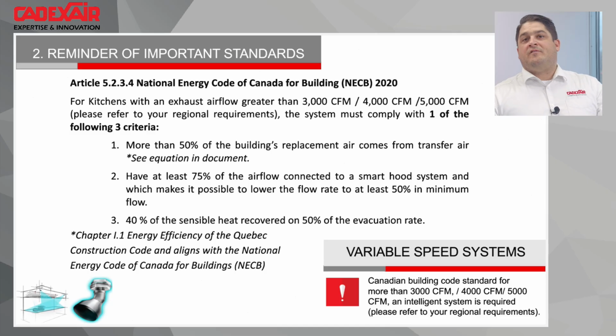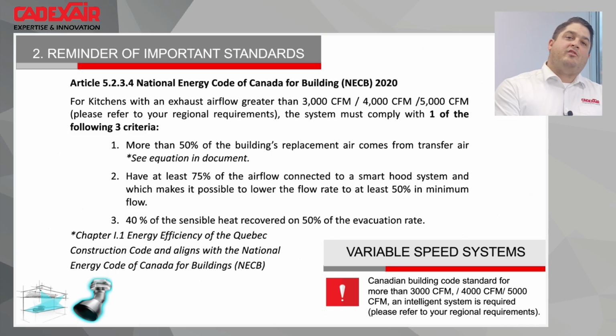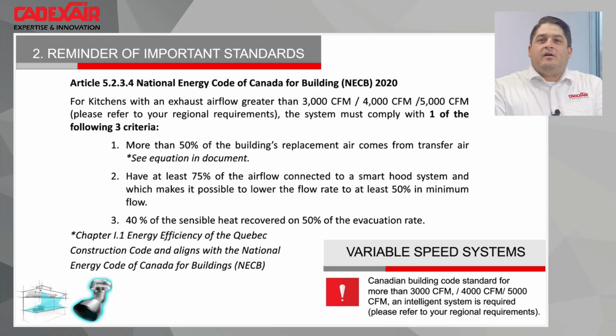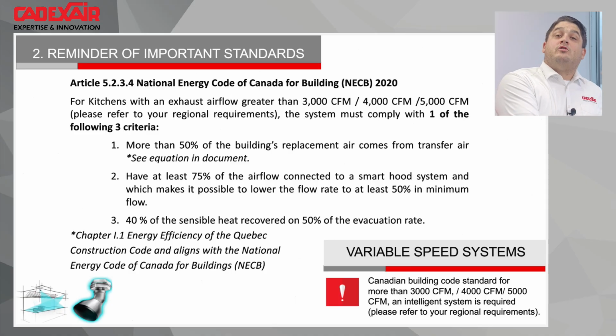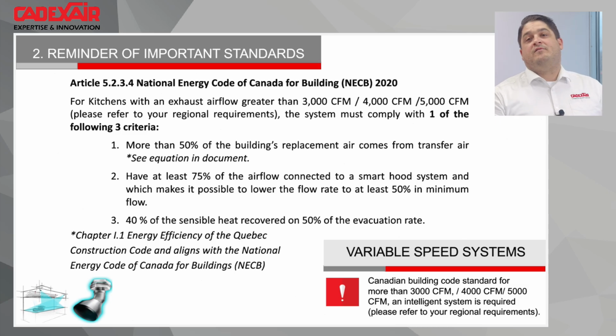The other possibility is to have thermal heat recovery on the kitchen exhaust hood system. I will not say I know every system in the world, but there are not a lot of heat exchangers. Normally, to use a heat exchanger in a system, you need heavy filtration. Buying filtration, putting in a coil to save on the demand control system, that's too expensive, and you also need to change the filter, which brings more cost. So at the end of the day, if you want to do heat recovery, you need a pollution control unit. If you're stuck with a pollution control unit, you can put in an energy recovery coil to save some money. So now I will try to explain what the difference is.